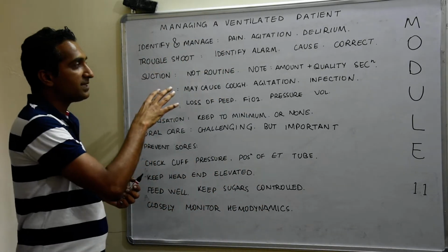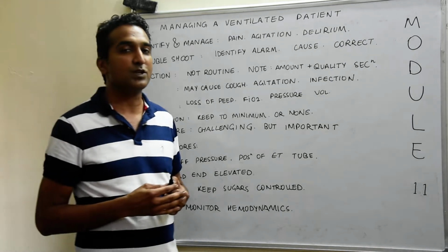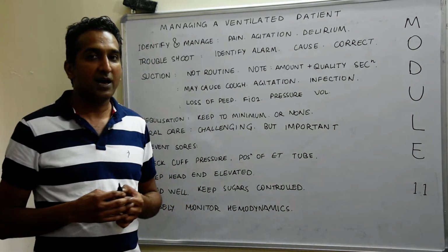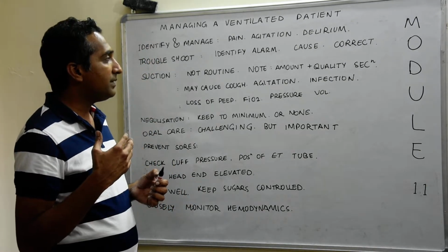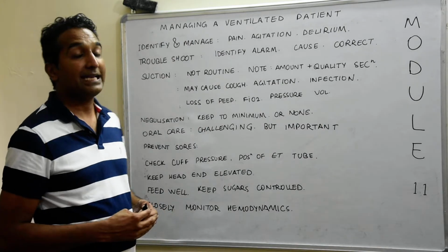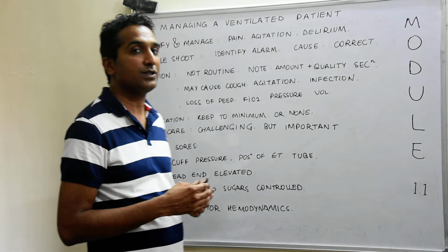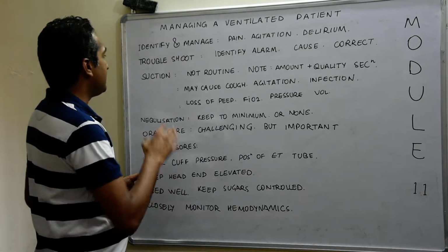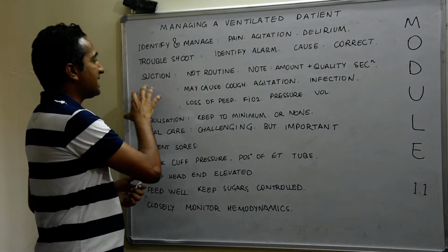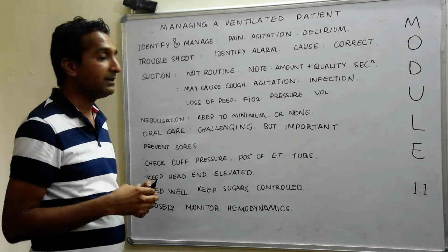Troubleshooting the ventilators, you need to know what settings the patients are on, why there is an alarm, finding the root cause and correcting it so that you see the patients and the ventilators are well synchronized. The one important aspect which comes is of suctioning.